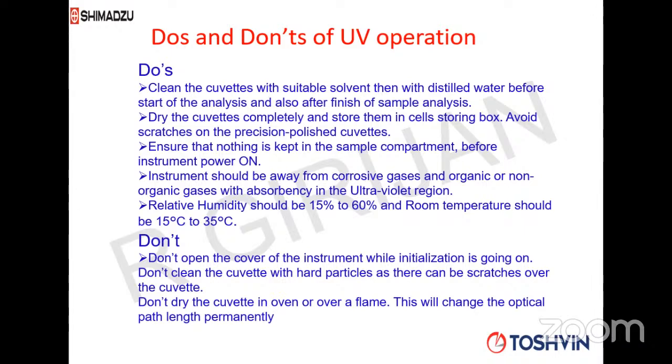So rinse the cuvette, clean it well, rinse with the solvent, and just keep it on your table for 5 minutes and it will automatically dry. You can give a rinse with acetone or something, and it will dry automatically. And if after so many usages you feel there is something sticking to the side, maybe on a weekend, you can put this cuvette in a dilute chromic acid solution overnight. Chromic acids are very, very powerful oxidation systems. The next day morning when you come, you can take it out, wash in plenty of water, finally rinse it with distilled water, and give a final rinse with good quality acetone, air dry, keep it on the table. And this will become very, very clean.